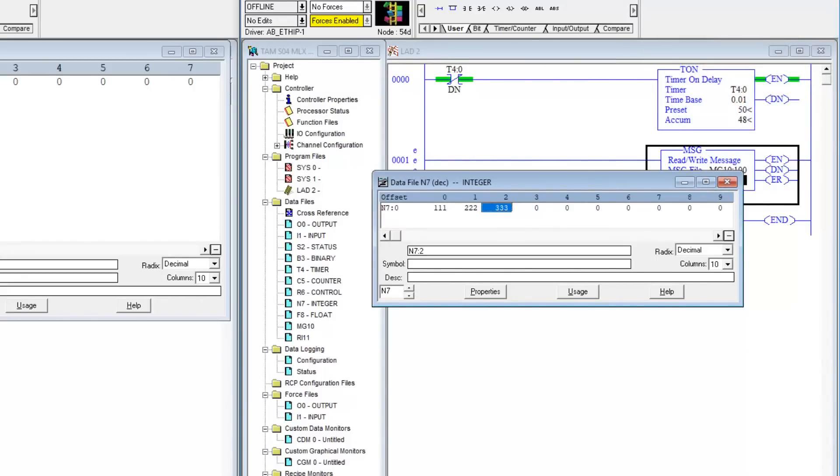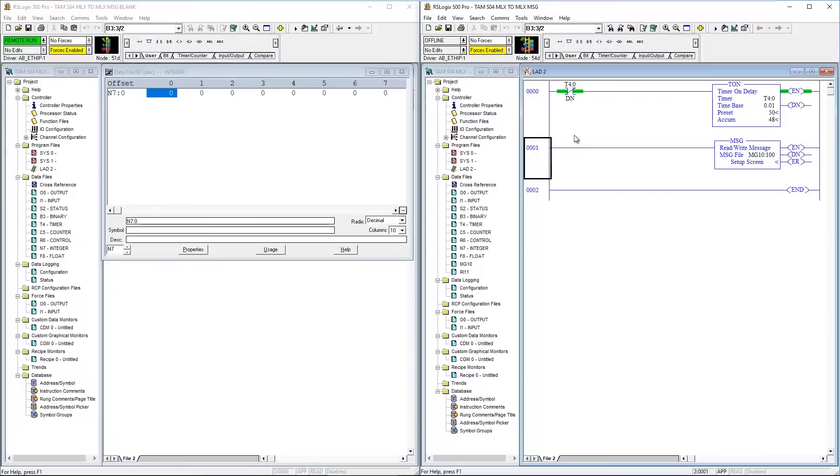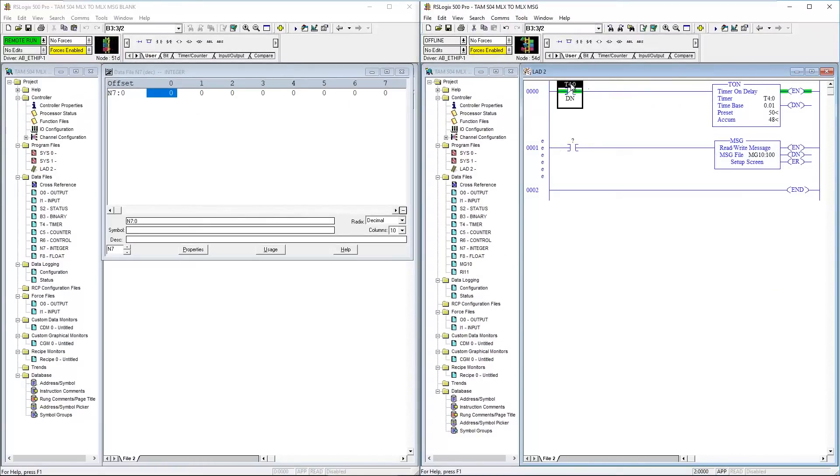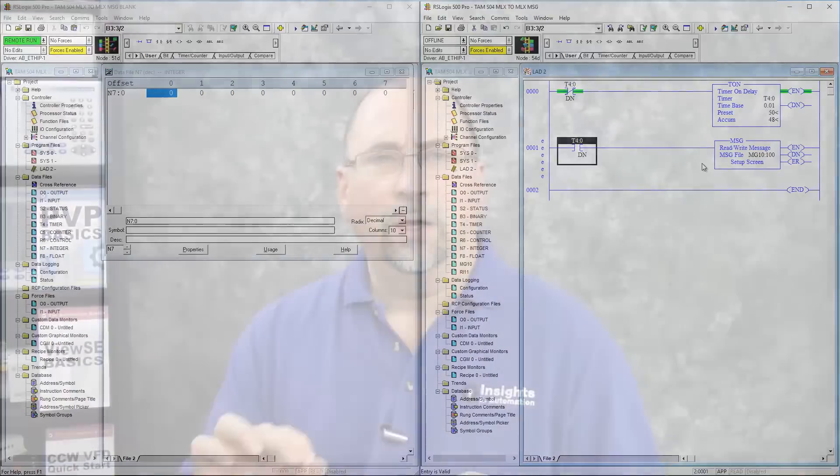Now at this point, I'm going to also add in an XIC to trigger that message every half second. The reason I'm doing that is because I don't want this to be a continuous message, because if you have too many of those, you can overfill your buffer in the Micro and then you'll lose some of your messages.